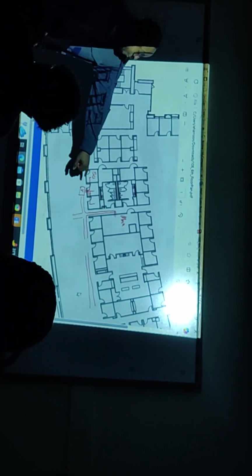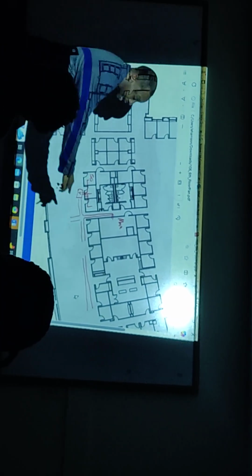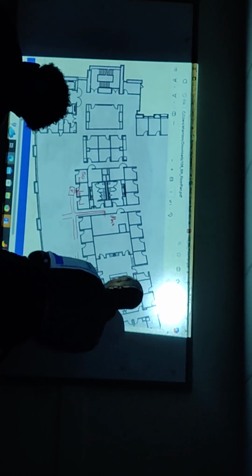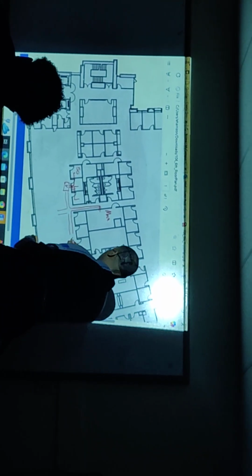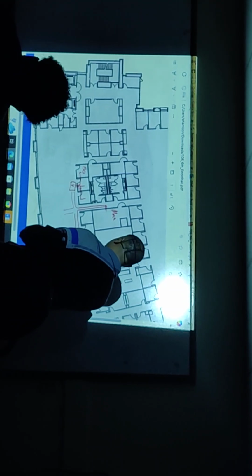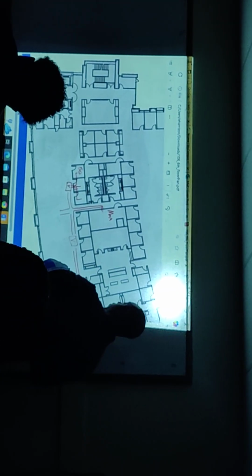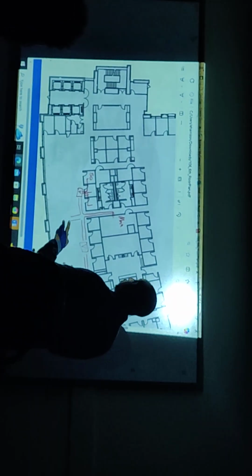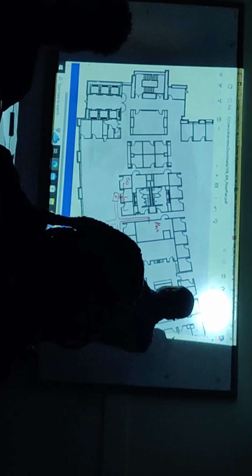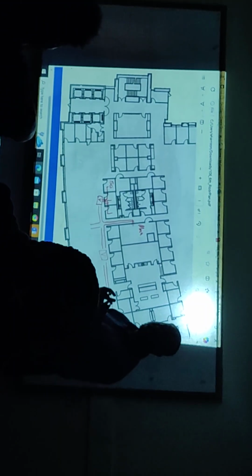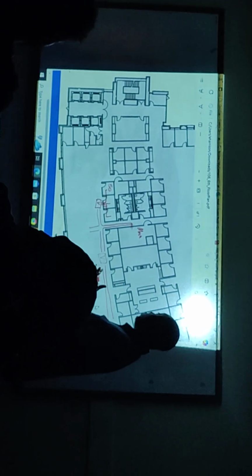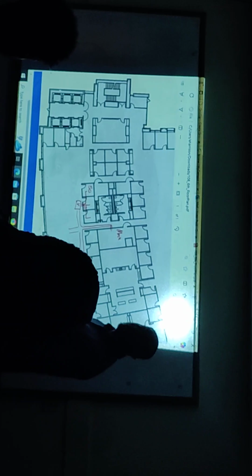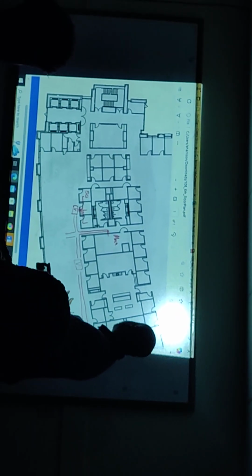All right, so VAV, I'm going to put a VAV here to do these 3. I see I got about 4 rooms. I got a cluster, so I'll probably do a VAV for all 4 of those. So I'm going to go ahead and put a VAV here. All right, and again, you can wait on your ductwork. You don't have to. That's what you were asking me. Just get your VAV location first. That lets you know where you want to run your ductwork. If you go ahead and start running ductwork, it might not make any sense, or your stuff is going to be messed up.